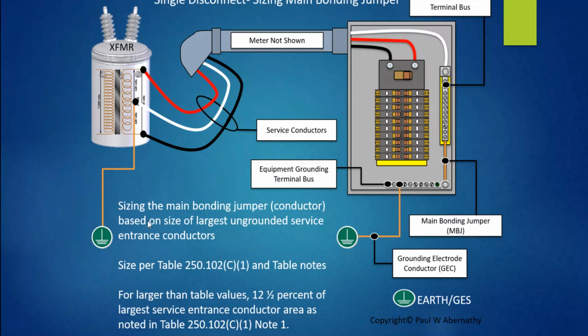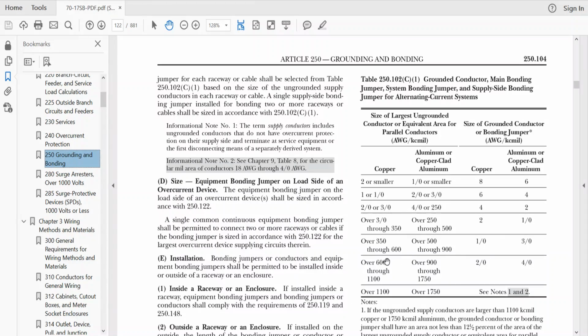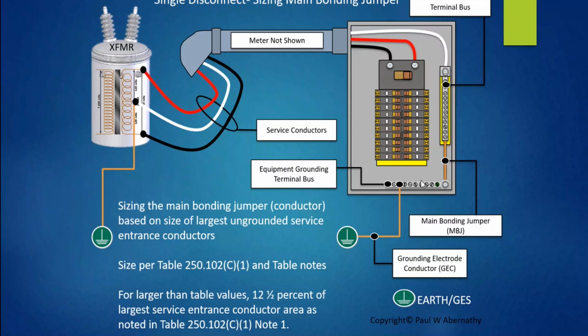The size of the main bonding jumper conductor is based on the size of the largest ungrounded service entrance conductors. So in this case up here, that's what we're going to do. Now, what size would that be? Well, if it was a 500 kcmil coming in for whatever reason, then I have to go to this table. So here we're going to the NEC, and we'll see on the right that if it's copper, and we always assume copper unless stated otherwise, and it is over 350 through 600, then it's going to be a 1/0 right here. Over 350 through 600 would be a 1/0. So let's go back to the presentation. This main bonding jumper right here would be a 1/0, sized based on the largest service entrance conductor supplying this piece of equipment.